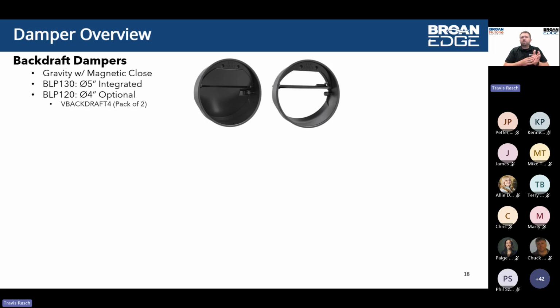I haven't mentioned the model numbers yet, but again, we're going to have gravity dampers that have a magnetic close feature on them. So once they close, they stay closed until the unit turns back on, and that airflow blows those dampers back open. The BLP 130 model will have 5-inch ducts on it, and it will have these dampers included with the product itself. The damper basically sits inside the port of the product.